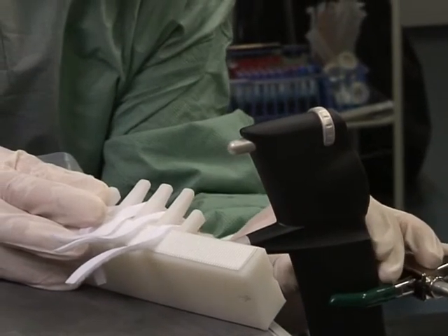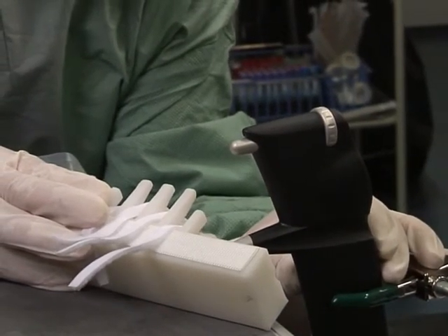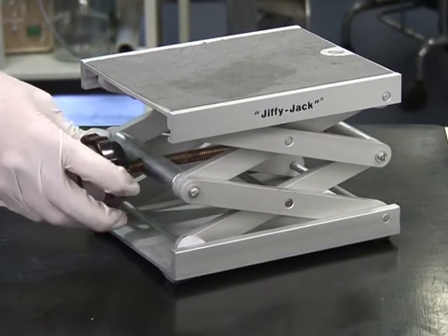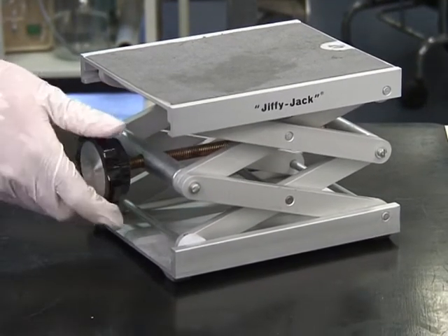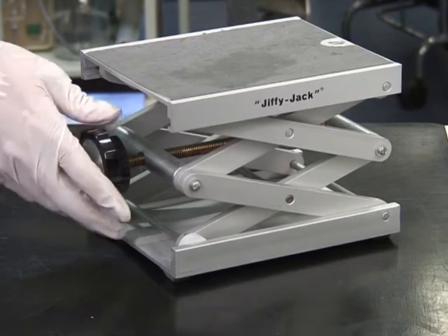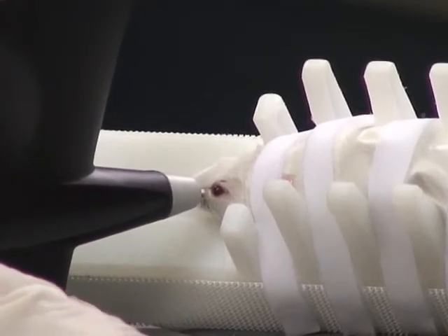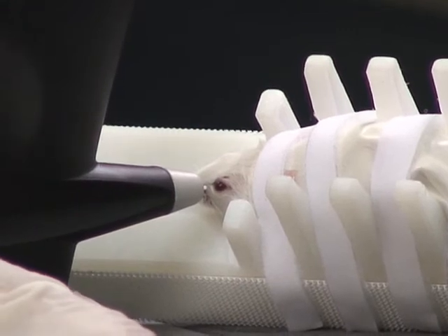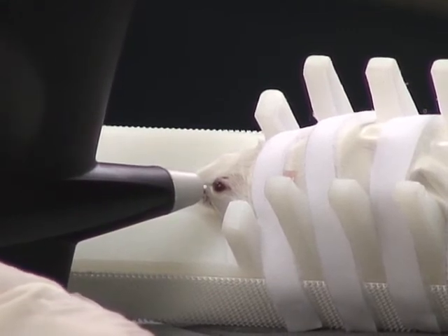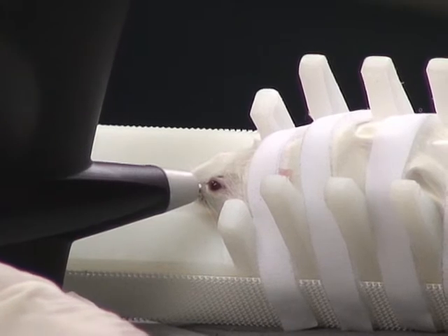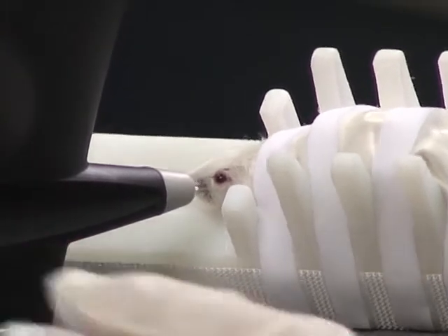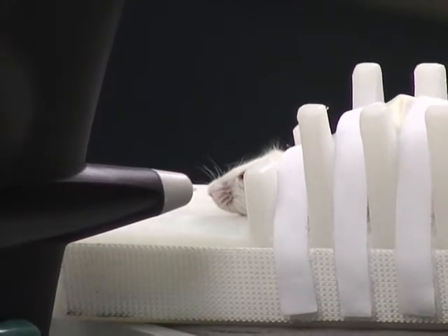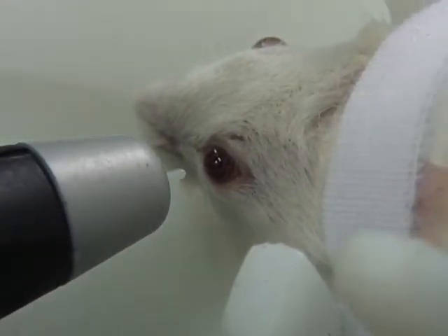One hand holds the restrainer at the rear and brings the mouse eye near the probe tip. Tilt the restrainer and adjust the height of the platform until the probe tip has a perfect alignment with the optical axis of the eye and can hit the very center of the cornea. The distance is about 2 to 3 millimeters from the probe tip to the surface of the cornea. IOP can then be measured by pressing the measurement button using the other hand.